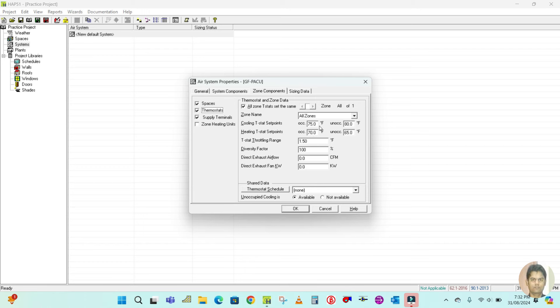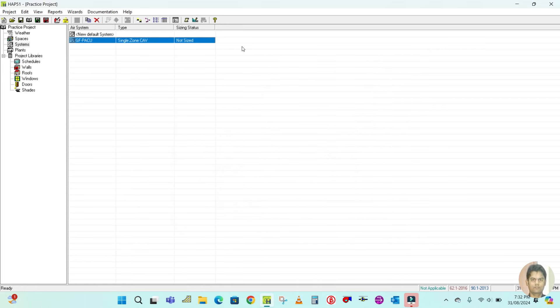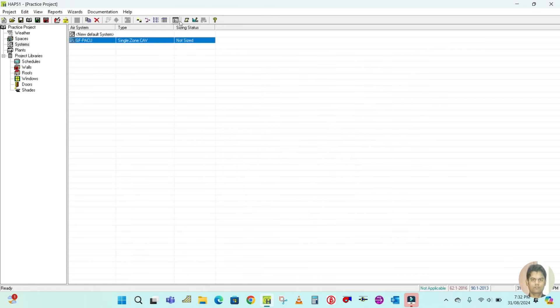For the ducted system, duct heat gain you should keep at five percent, and duct leakage is five percent. Then go to the zone and component section, where you can select all the ground floor zones.